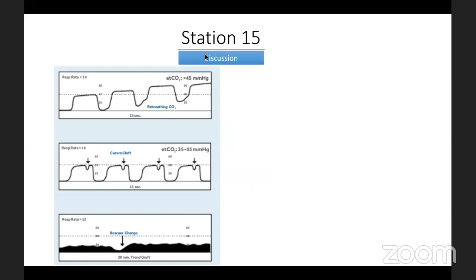Okay. So what exactly is the indication for change of soda lime? The question is, when do you change soda lime? If it indicates a color change. Color change is one thing, but it is not fully reliable because over the weekend it can regain a bit of color and it will get easily exhausted in the initial hours of the day. The second one is appearance of inspiratory CO2. If it is more than 5, definitely you have to change. Initially, you can manage with higher fresh gas flows.